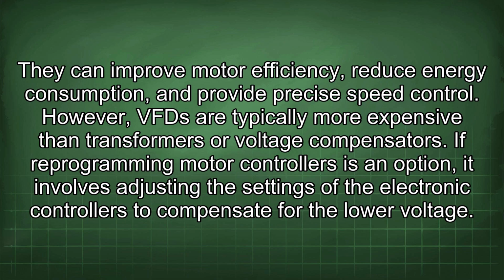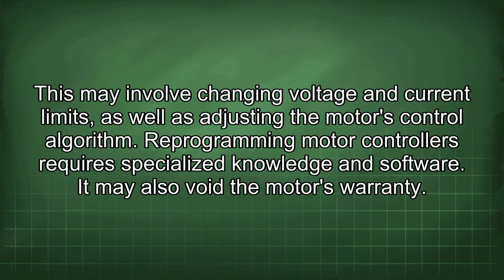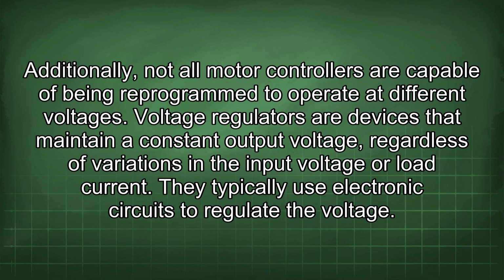If reprogramming motor controllers is an option, it involves adjusting the settings of the electronic controllers to compensate for the low voltage. This may involve changing voltage and current limits, as well as adjusting the motor's control algorithm. Reprogramming motor controllers requires specialized knowledge and software. It may also void the motor's warranty. Additionally, not all motor controllers are capable of being reprogrammed to operate at different voltages.